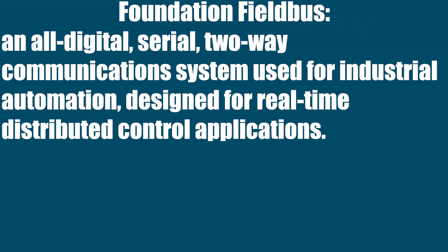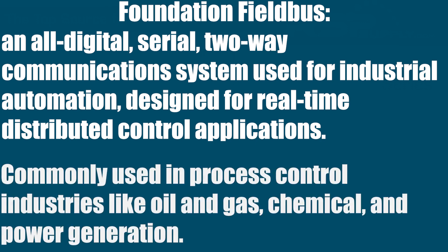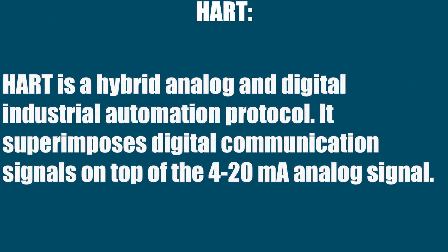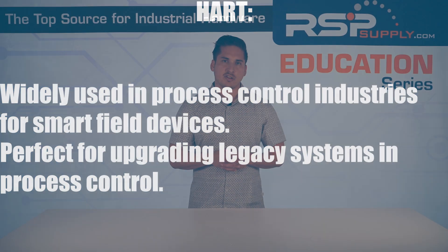Foundation Fieldbus is an all-digital, serial, two-way communication system used for industrial automation, designed for real-time distributed control applications. It's often used in process control industries like oil and gas, chemical, and power generation. You also have HART — Highway Addressable Remote Transducer — a hybrid analog and digital industrial automation protocol. It superimposes digital communication signals on top of the 4-20 milliamp analog signal, and is very often used in process control industries for smart field devices. It's perfect for upgrading legacy systems in process control.